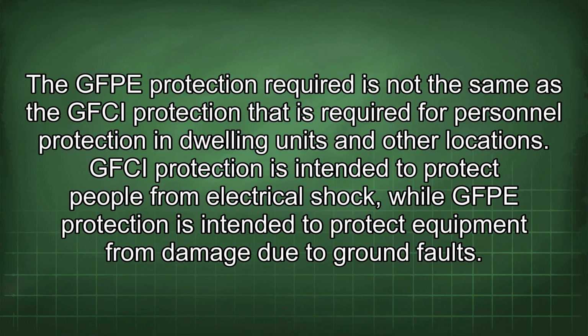The GFPE protection required is not the same as the GFCI protection that is required for personnel protection in dwelling units and other locations. GFCI protection is intended to protect people from electrical shock, while GFPE protection is intended to protect equipment from damage due to ground faults.